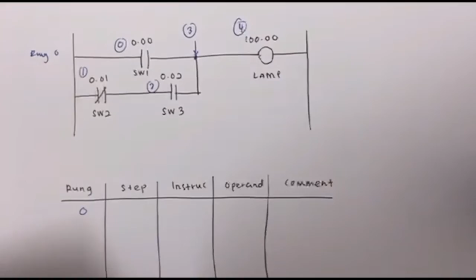So step 0: since this is a normally open contact, the instruction is LOAD, the operand is 0.00, and the comment is switch 1. Step number 1, moving downward: since it is a normally closed contact, the instruction is LOAD NOT, with its operand and comment. Moving to the right, the second step is AND, since it is in series connection while this one is parallel, with 0.02 and switch 3.